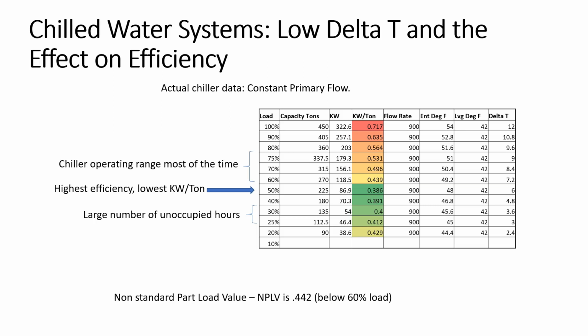Okay, so if we're out there doing audits and we look at the chill water supply and return, we have trend logs and all that, and we see that they're often at 3 degrees or 4 degrees, it means there's an opportunity. And let's say maybe there's not a variable frequency drive on the chill water pump, but that means there's an opportunity for savings. Exactly. Yes, and this machine will handle it, they just didn't do it. Okay. And that was their complaint. The NEBB company, the company that did the job, was trying to figure out why they weren't running it more efficiently. And it turns out it was this flow issue.